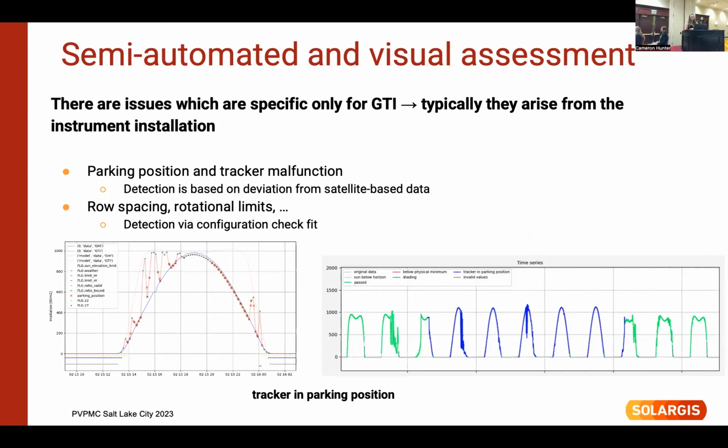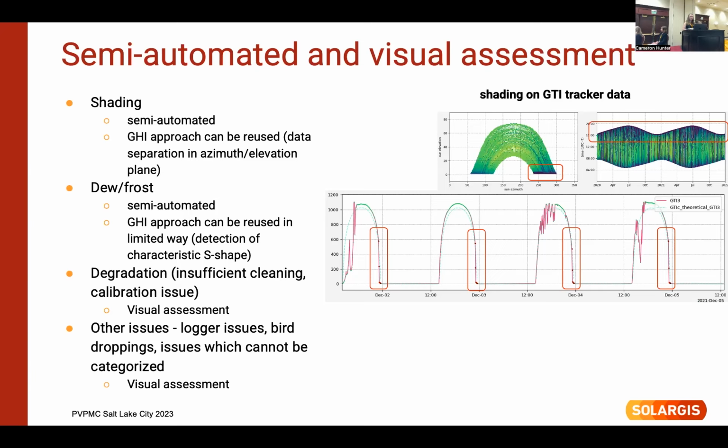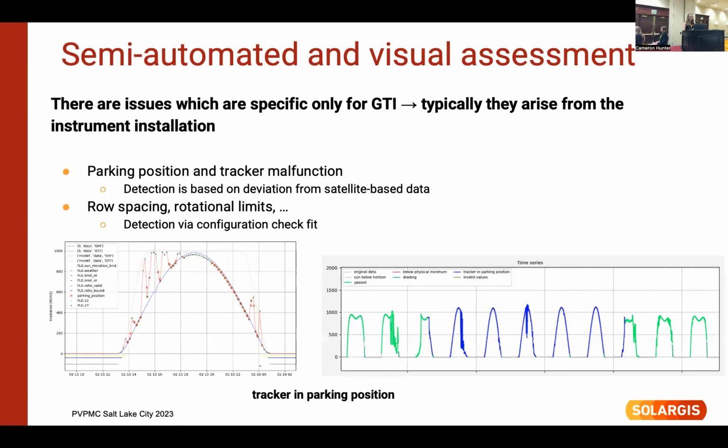Okay, so this was something we already have for GHI. We tried to apply it for GTI. It worked somehow, partially. But in GTI, we have other issues which are not present for GHI. And as I mentioned before, they typically arise from the instrument installation.